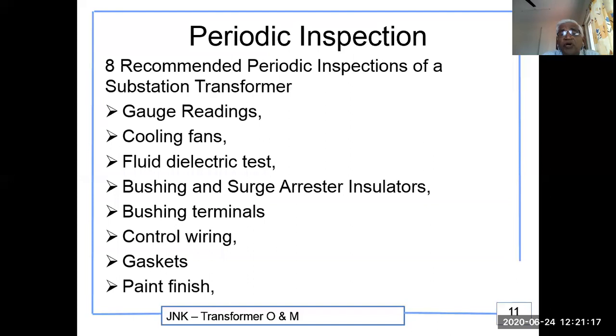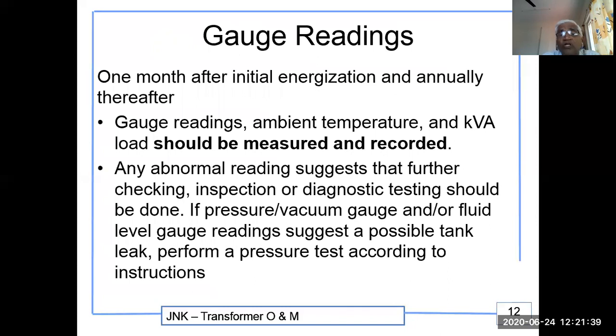Periodic inspection. Eight recommended periodic inspections of a substation transformer are gauge readings, cooling fans, fluid dielectric test, bushing and surge arrestor insulators, bushing terminals, control wiring, gaskets, and paint finish. Gauge readings: 1 month after the initial energization and annually thereafter, gauge readings of ambient temperature and kVA load should be measured and recorded. Any abnormal reading suggests that further checking, inspection or diagnostic testing should be done.